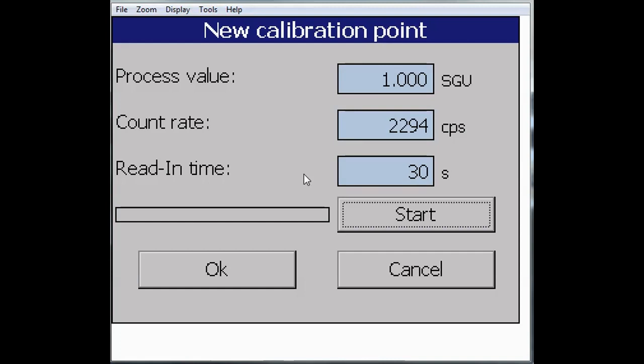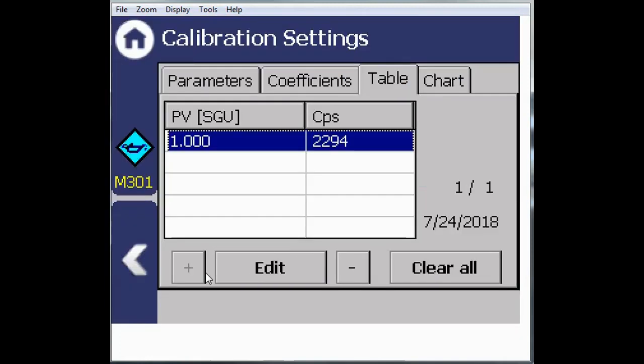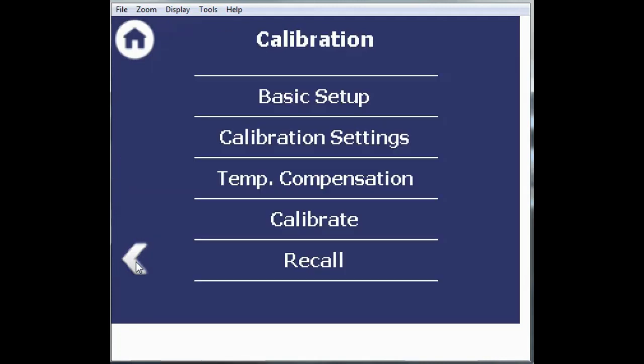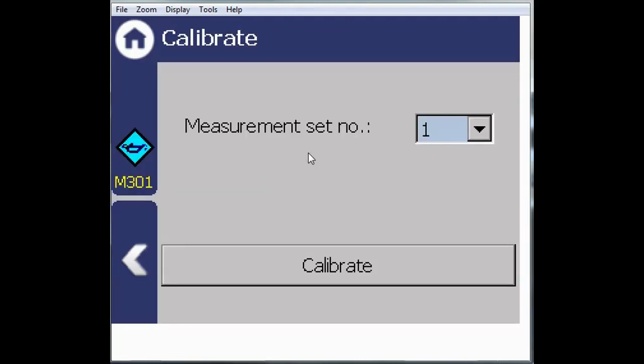The read-in is complete. We have our counts for our process value. Select OK, and you see it populated in the table. Select the back arrow and calibrate. We are setting the measurement set number 1. You can set different measurement sets if you have different products flowing through the same pipe, but you will have to trigger this from an outside source so the gauge knows exactly what product you have in the pipe at that moment. Since this is measurement set 1, we'll click Calibrate.